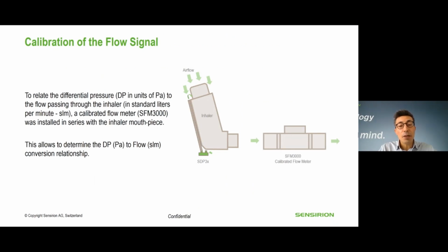The measurement principle of the clip-on device is based on the correlation between the airflow through the flow sensor and the airflow through the inhaler. In order to obtain the correlation factor for different flow rates, we calibrated the clip-on device by using one of our mass flow meters, SFM3000, as a reference, translating the pressure in Pascal into flow signal in liter per minute.